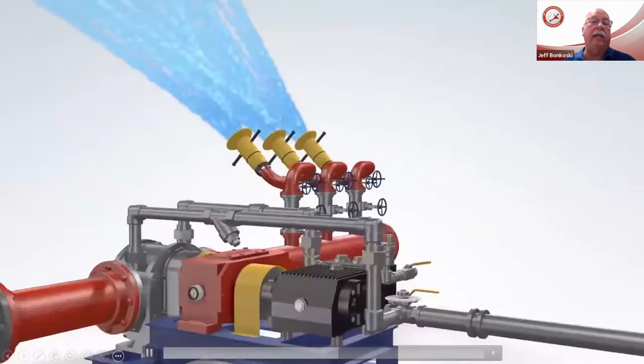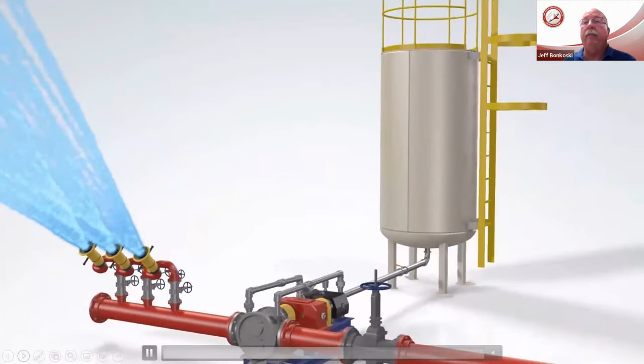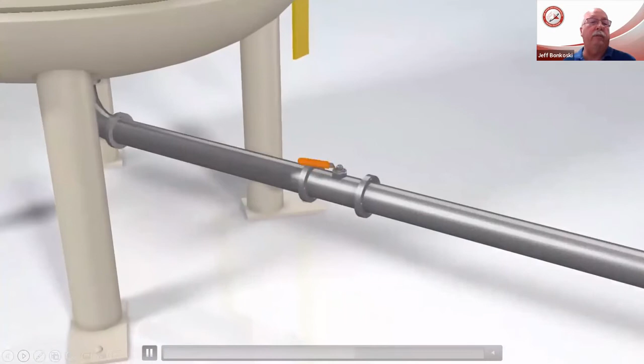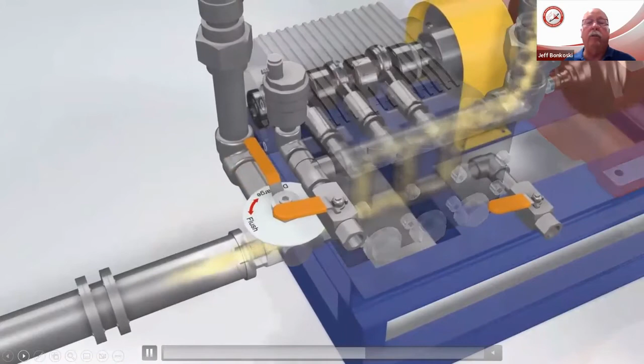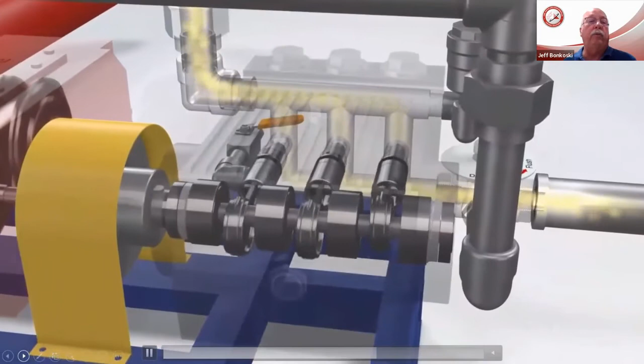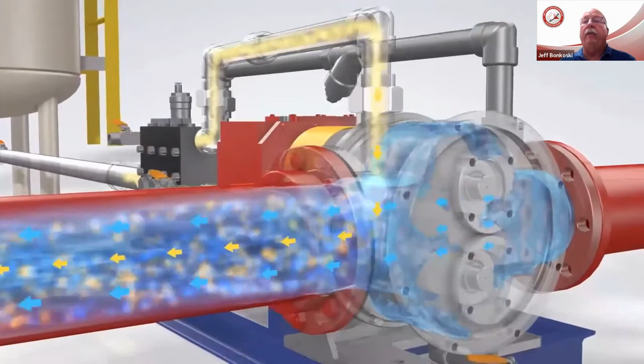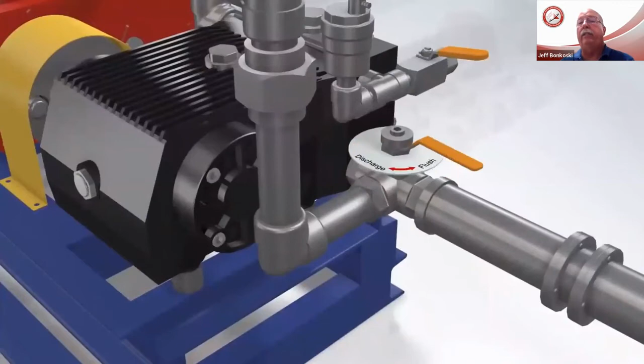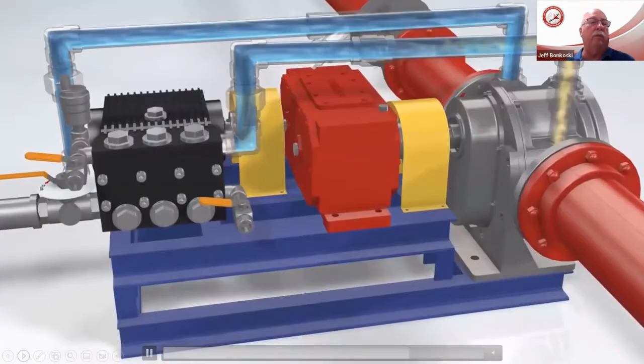Based on the occupancy or the fire load, if it's flammable liquids, lithium ion batteries, or class D metals, you're looking at 3%. If we're looking more towards class A, we're looking at 1%. Those percentages for the occupancy and the fire load will be calculated, and then the duration, your flow times, and all those things will be worked out, and we'll work with you to help with that design.